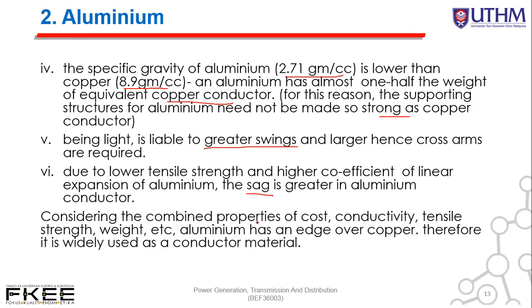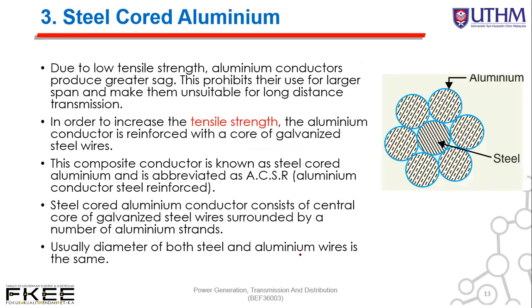Considering the combined properties of cost, conductivity, tensile strength, weight, and so on, aluminum has an edge over copper. Therefore, it is widely used as a conductor material. Now we see the steel core aluminum. Due to low tensile strength, aluminum conductors produce greater sag.